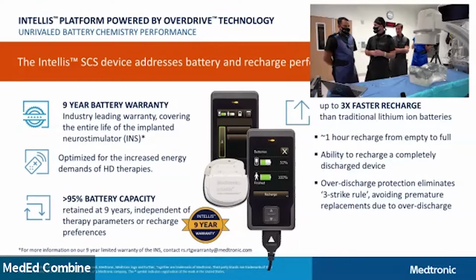And why is that important? Because when you have to switch out the batteries for these patients, it's a surgery. Yep. They have to go into the operating room. You have to incision, chance of infection, everything that has to do with a surgery. It's not just like your phone, take out the battery, put one in.